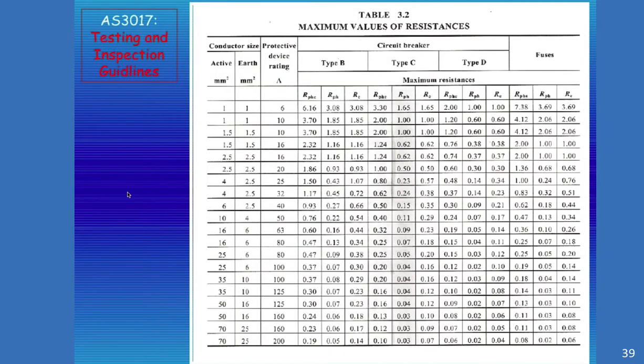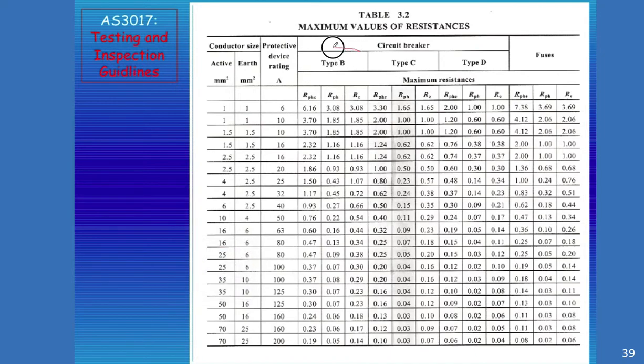Here's our table again from AS3017. And I've just put this here to remind you that circuit breakers come in B's, C's, and D's. Fuses are all grouped together over here. And this particular table tells us the maximum values of resistance for different components within the loop, depending on the size of your active, the size of your Earth, and the protective device's current rating.